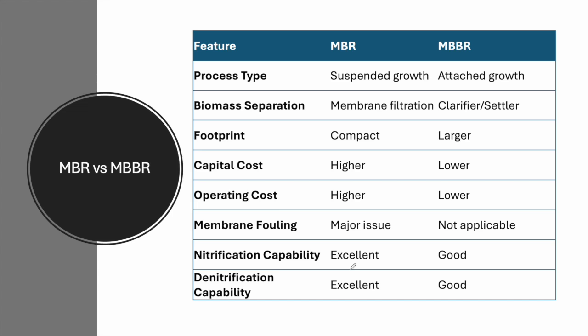Now let's go more in depth on the comparison. For the MBR, we have a suspended growth process with advanced membrane filtration. For the MBBR, we have attached growth — microorganisms attach to the MBBR media. Biomass separation for the MBR is through membrane filtration; for the MBBR it is through the secondary clarifier, where activated sludge settles. For footprint, the MBR is more compact than the MBBR.